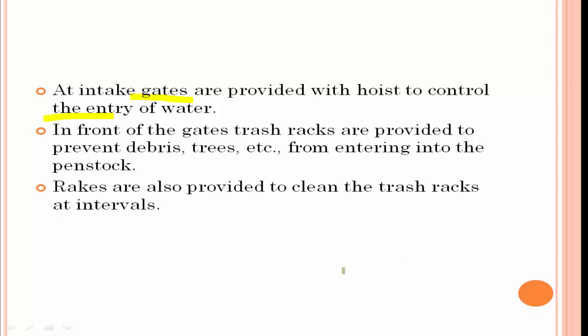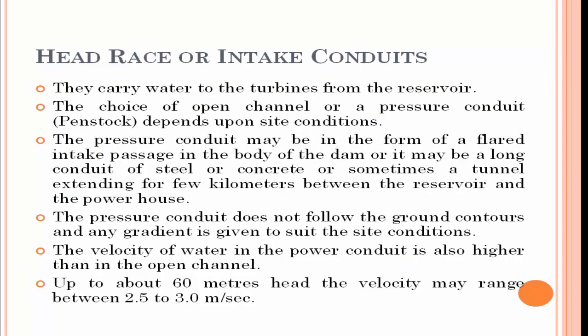Next is the head race or intake conduits — this is the second stage. They carry water to the turbines from the reservoir. We have two categories: open channel and pressure conduits. The open channel will be completely open with water flow, whereas pressure conduits are like a pipeline. The pressure conduits may be in the form of a flared intake passage in the body of the dam, or long conduits of steel or concrete, sometimes a tunnel extending for a few kilometers.